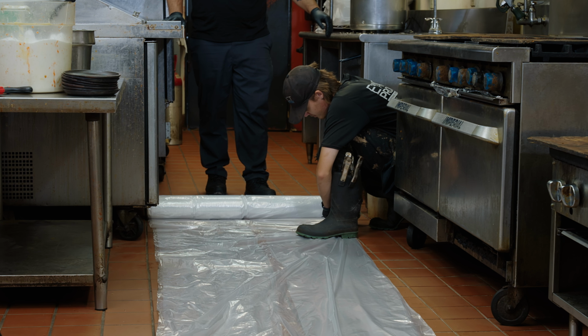Spraying up into the plenum, make sure you're hitting the rail that the filters slide into inside of the plenum. Make sure that whenever you're hitting the plenum, you're spraying that out so that when you go to put the filters back in at the end, they can properly go in.